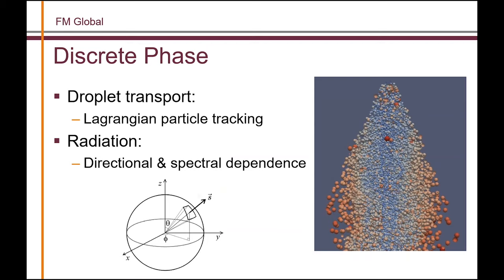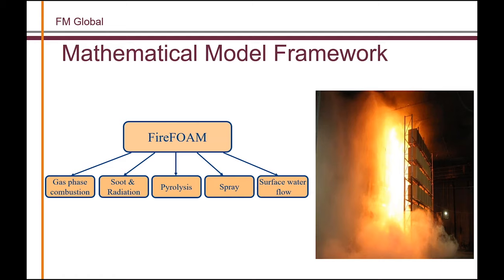In addition to the overall mesh zones, we also solve the discrete phase — the transport of droplets tracked in a Lagrangian way. Their drag, heat transfer, and evaporation process need to be captured. On top of that, there is a radiation calculation, which depends not only on the spatial mesh but also on direction and wavelength. This is a very complex mathematical implementation of all the different physics, and together they are put into the mathematical framework within FireFOAM to capture the fire suppression phenomenon.